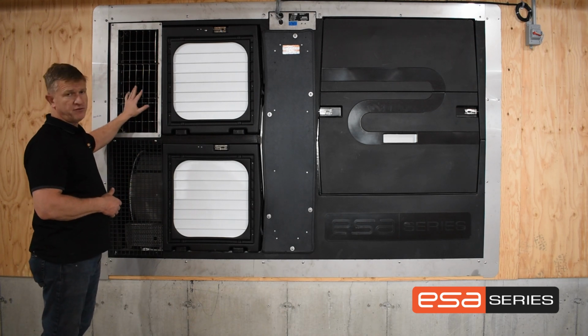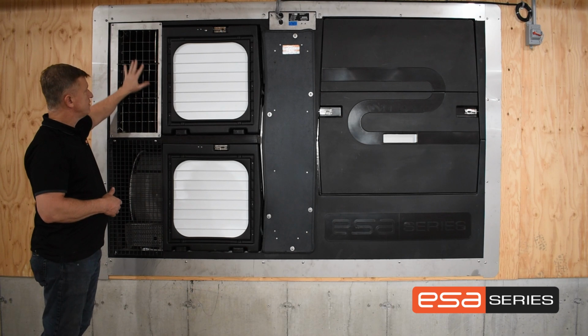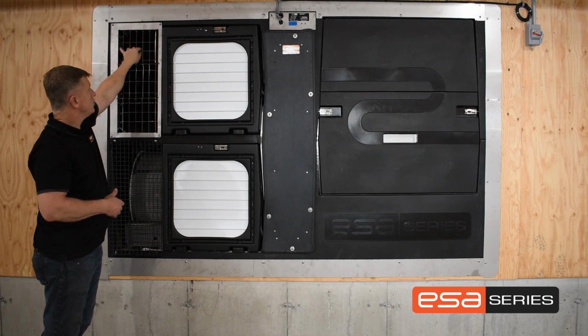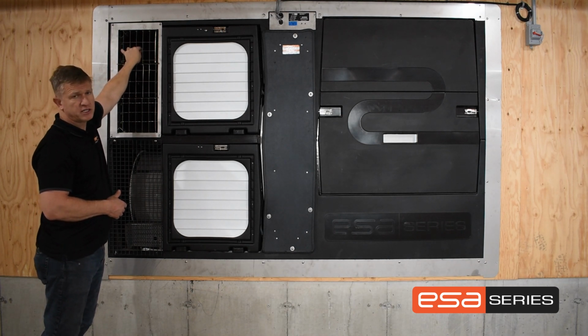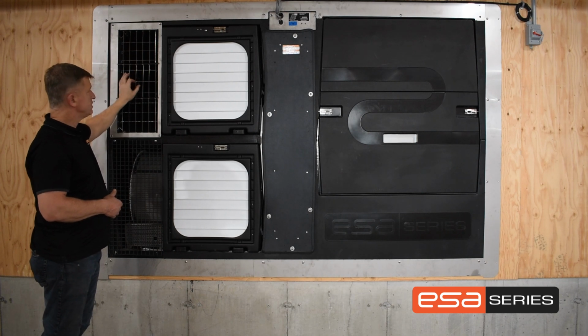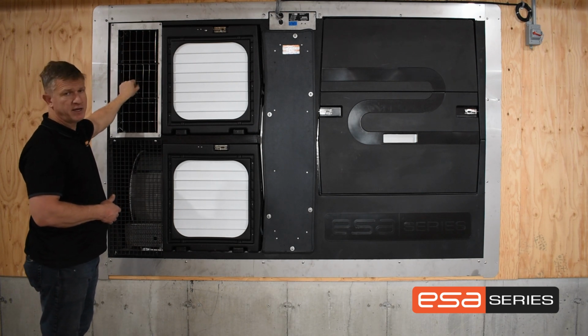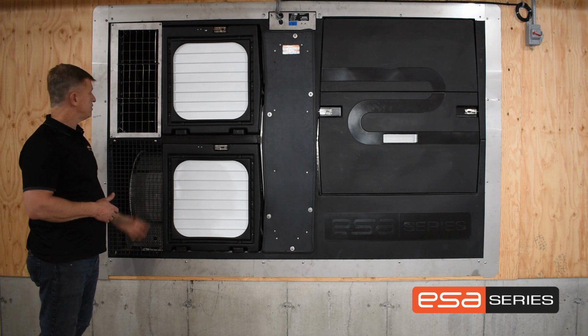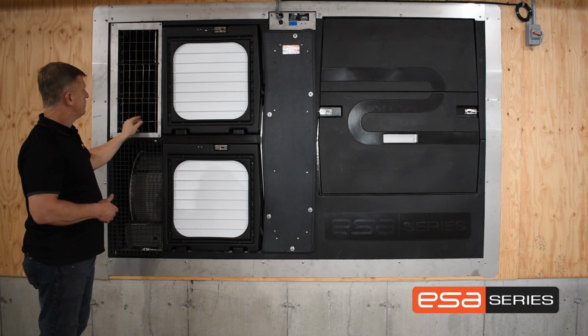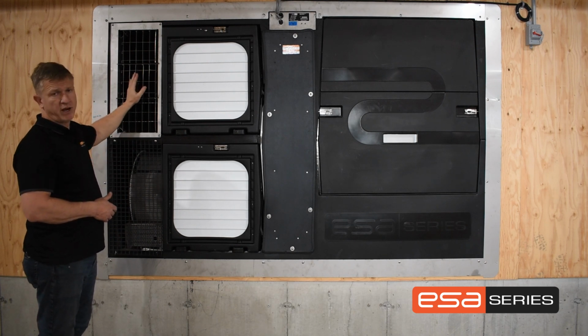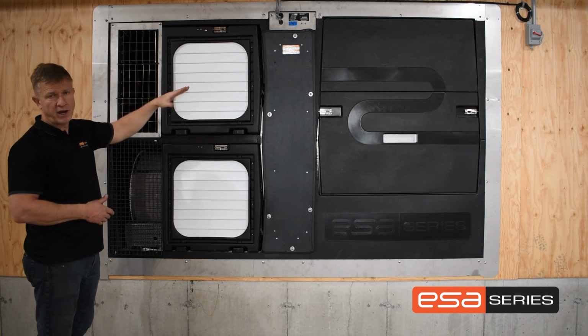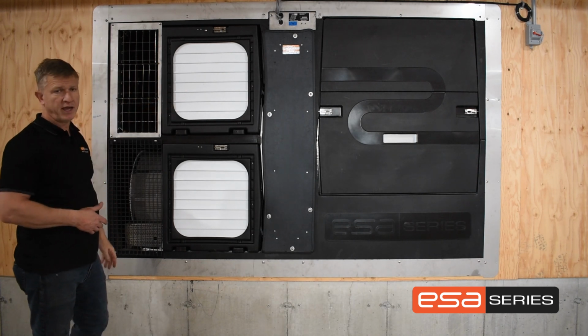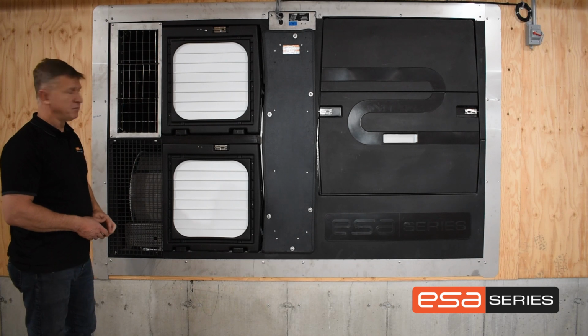As you can see, this diffuser has 3 sets of louvers. You've got some in the back which allow you to adjust up and down, and the ones in the front you can adjust left and right to give you directional flow on your air. Some of these you can point left, some you can point right, and some you can point straight ahead, depending on what your air pattern is in the building.